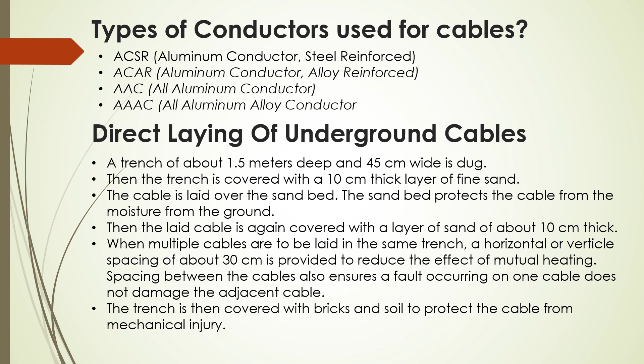Then the laid cable is again covered with a layer of sand about 10 cm thick. When multiple cables are to be laid in the same trench, a horizontal or vertical spacing of about 30 cm is provided to reduce the effect of mutual heating. Spacing between the cable also ensures the fault occurring on one cable does not damage the adjacent cable. The trench is then covered with bricks and soil to protect cable from mechanical injury.